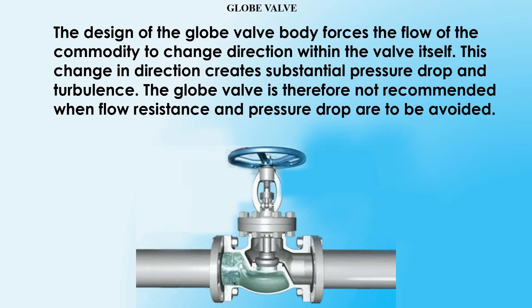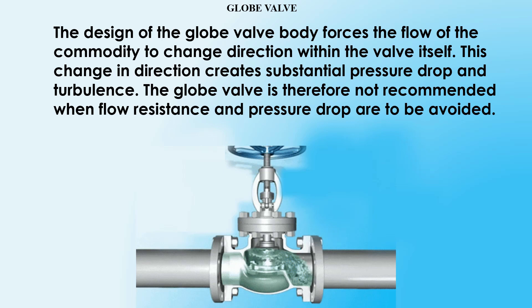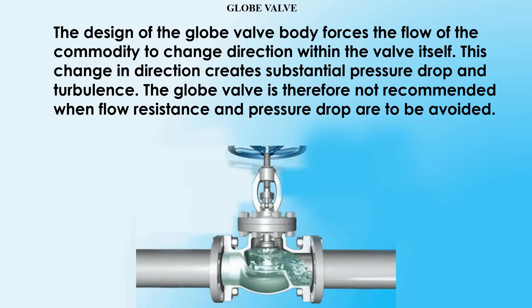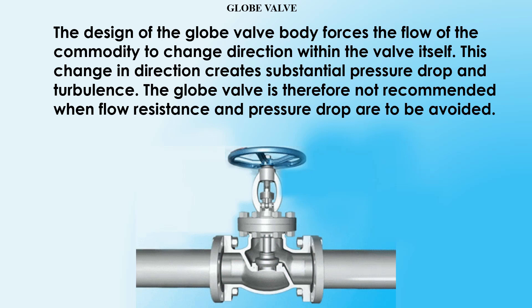The design of the globe valve body forces the flow of commodity to change direction within the valve itself. This change in direction creates substantive pressure drop and turbulence. The globe valve is therefore not recommended when flow resistance and pressure drop are to be avoided.